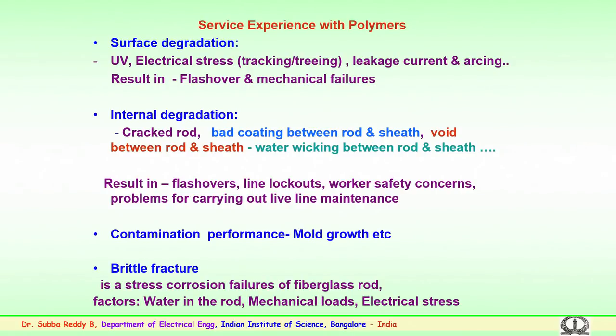The important part, as mentioned and discussed earlier, is that the contamination or pollution performance of these insulators in the field is a very important factor for design consideration. I am mentioning it several times. The contamination performance dictates the insulator, particularly in the higher EHV and UHV, ultra high voltage, range. So, we will be discussing in detail the phenomena of contamination and pollution, how the failure happens at normal conditions, and what could be the reasons for failures at the working stresses.